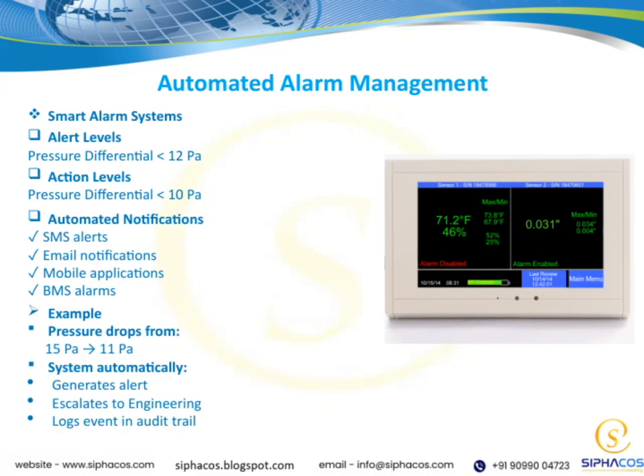Let's talk about automated alarm management and how smart alarm systems keep us ahead of potential issues. We set alert levels based on pressure differentials: under 12 pascals triggers an alert, and under 10 pascals demands action. When pressure drops from 15 to 11 pascals, the system doesn't wait. It immediately generates an alert, escalates the issue to engineering, and logs everything for review. Notifications come through SMS, email, mobile apps, and building management systems, keeping everyone informed and ready to respond.